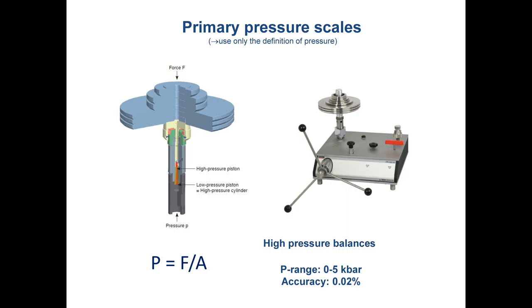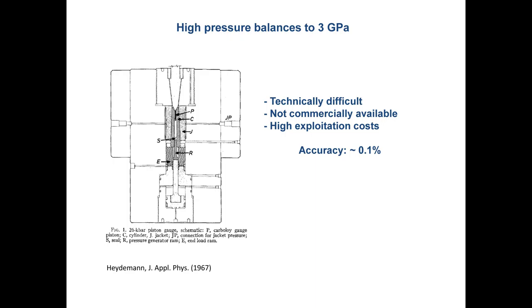At large-scale facilities, they have many pressure transducers that need to be calibrated, and they buy such machines for that purpose. But the limit is about 3 GPa — a piston-cylinder device doesn't work much beyond 1 GPa, as we heard from Konstantin. So you can push the pressure a little higher, but then it becomes very difficult. This is a high-pressure balance to 3 GPa — the limit of a piston-cylinder device.